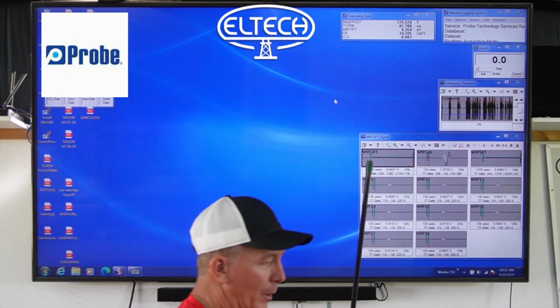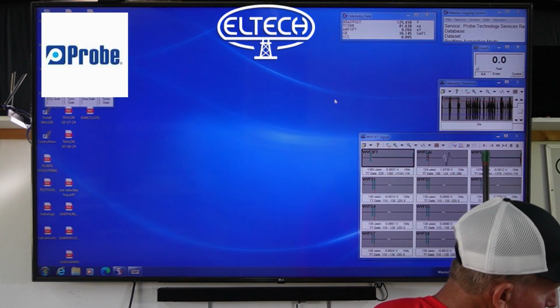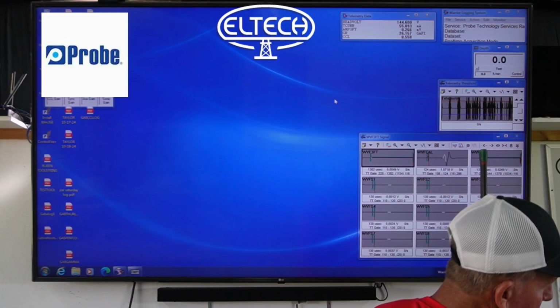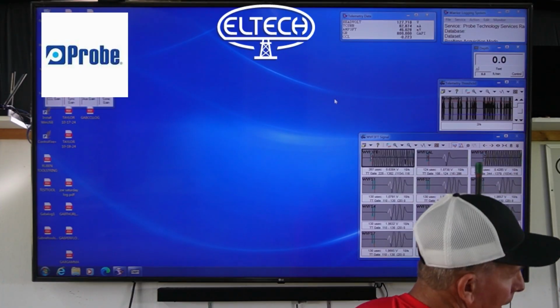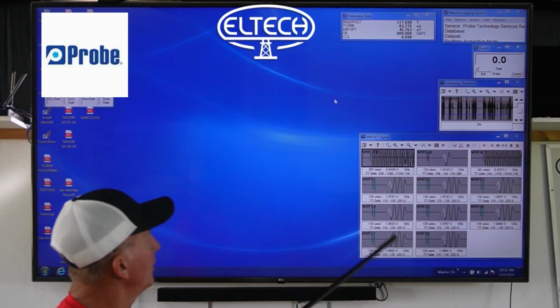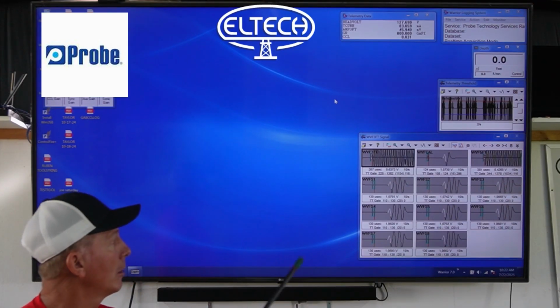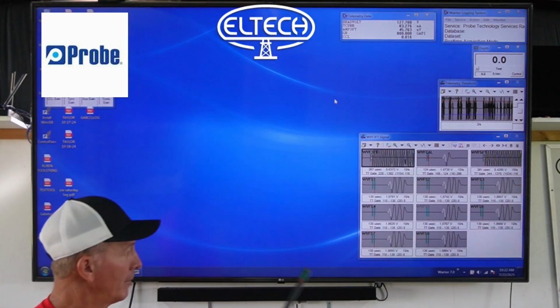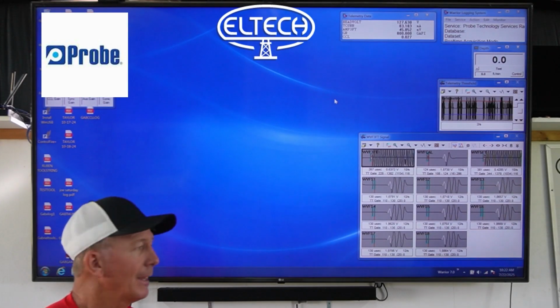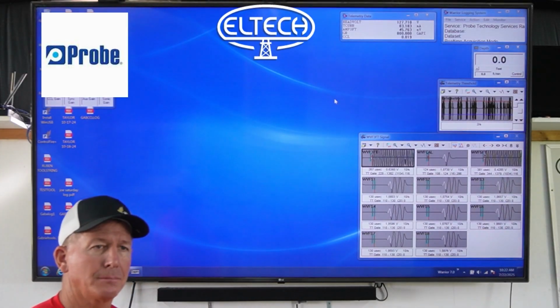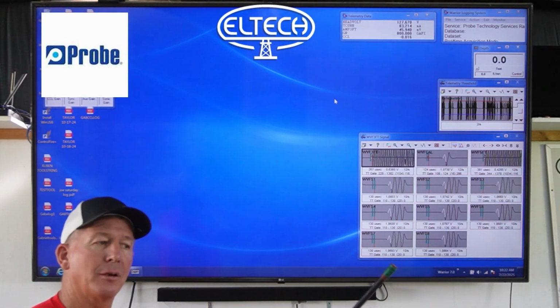So what we're going to do is roll up our voltage from 150 back down to 130. Okay, and you recognize all of a sudden now we're getting our signal coming into all our boxes. The 3-foot and 5-foot signals are all coming in. This is just a simulation, but it's great for us to get a calibration.